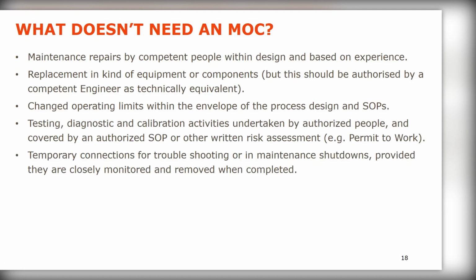Likewise, temporary connections - people have to troubleshoot. You inject signals and do all sorts of things to test things out. That's fine as long as it's closely monitored and removed. One of the big hazards is someone does a calibration on a pressure transmitter, isolates it, injects a signal into the transmitter, and forgets to de-isolate it afterwards. Then the control system just sees the last recorded pressure, which maybe doesn't change, so it's no longer effective.